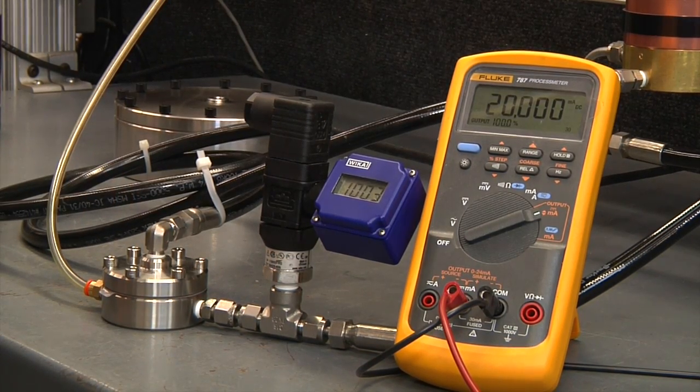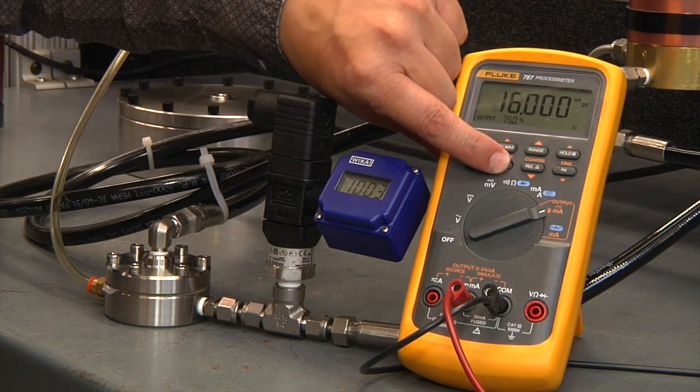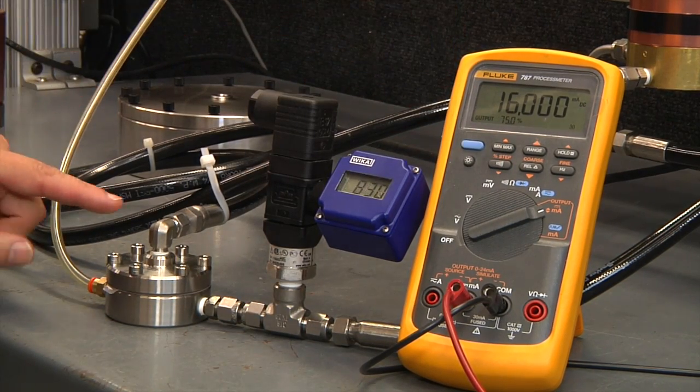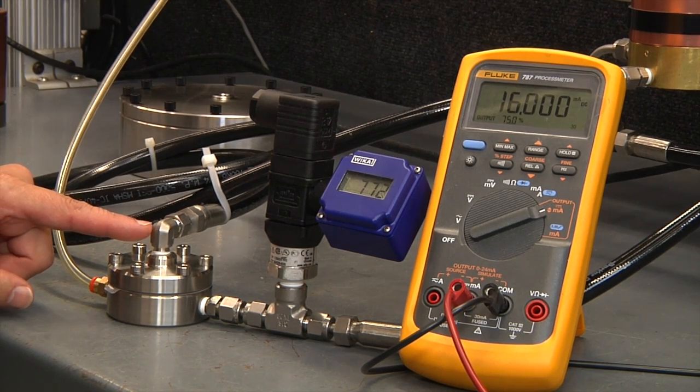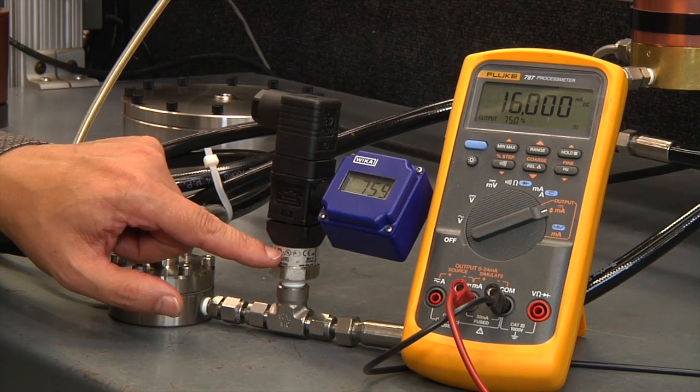The GX Series is a relieving regulator and by decreasing the command signal, we can reduce the pilot pressure on the back pressure regulator and therefore reduce the pressure in your system.